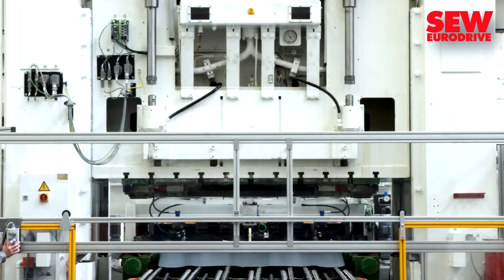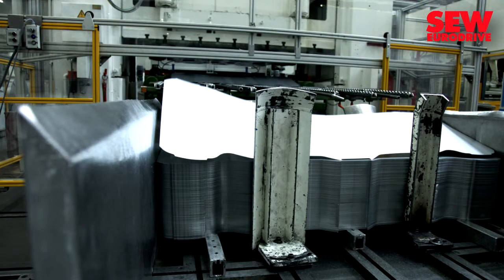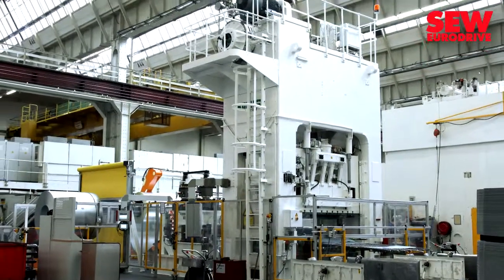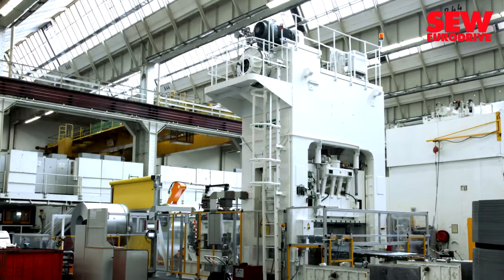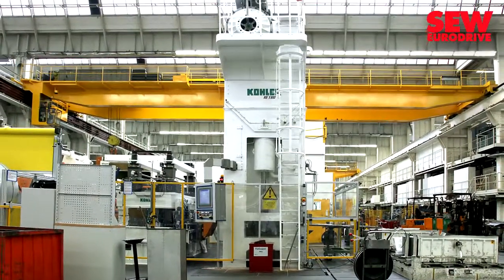The old machine had produced 15 sheet metal parts each minute. With the new drive technology, the speed has been doubled to 30 cycles per minute. Theoretically, even 45 cycles would be possible; however, this would cause the press to vibrate, which in turn would decrease quality. The drive technology from SEW operates the machine at the performance limit of the overall structure, while using 30% less energy than before.